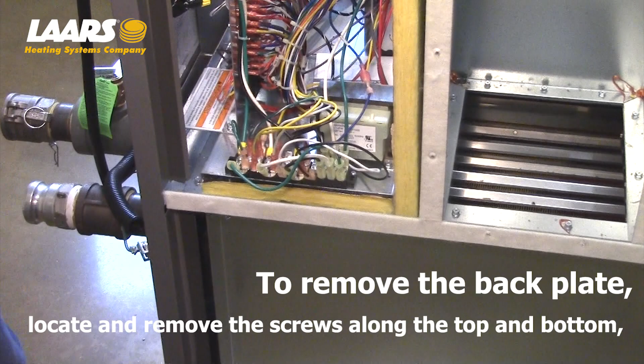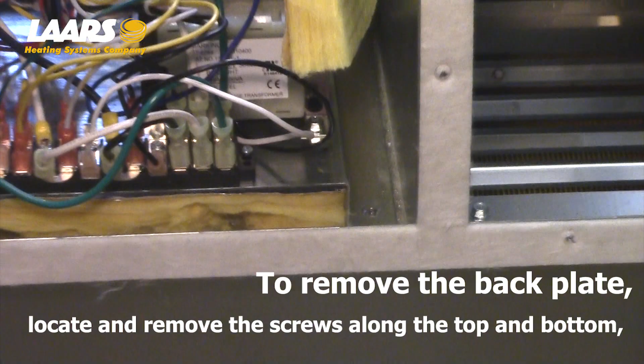On some of the boilers, you'll also have the electrical panel, and this plate is actually on top of those screws. So you'll have to remove the 5/16 screws for the electrical block to lift that up and remove the lower screws. The other option is to use an open end or box wrench to get in for the 5/16 screws.